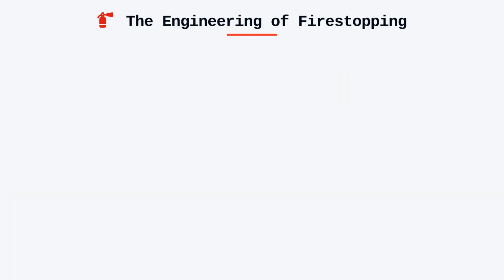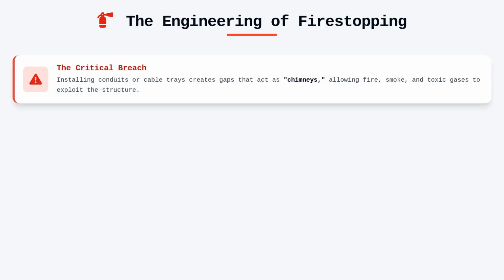Fire stopping is not merely a task of sealing a hole, it is a critical engineering function that preserves the fire rating of a structural assembly. When we penetrate a fire-rated wall or floor to install conduits or cable trays, we create a breach that fire, smoke, and toxic gases can exploit. The primary objective is to restore the barrier's integrity to match or exceed its original hourly rating.